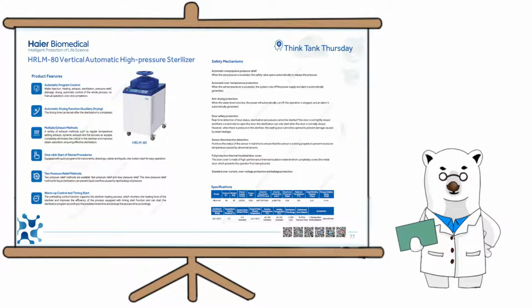Thirdly, multiple exhaust methods. A variety of exhaust methods, such as regular temperature setting exhaust, dynamic exhaust, and full process air escape, completely eliminate the cold air in the sterilizer and improve steam, ensuring effective sterilization. Fourthly, one-click start of stored procedures, which is very user-friendly. Fifthly, two pressure relief methods: fast pressure relief and slow pressure relief. The slow pressure relief method for liquid sterilization can prevent liquid overflow caused by rapid buildup of pressure. Lastly, warm-up control and timing start. It can be used to start the sterilization program according to the predetermined time and arrange the process time accordingly.